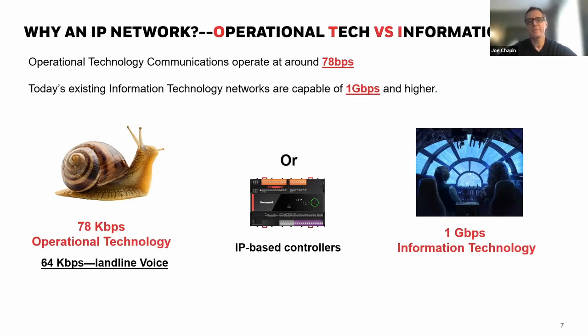When you install an IP-based controller that can connect to your Category 5 Ethernet cabling, you go to 1 gigabit. That means you went from a one-lane highway at 78 kilobits to a 12,800-plus lane highway with your 1 gigabit. This graphic really doesn't do it justice, but essentially you're going from snail pace to light speed pace by installing a new type of controller, the IP-based controller shown in the center.